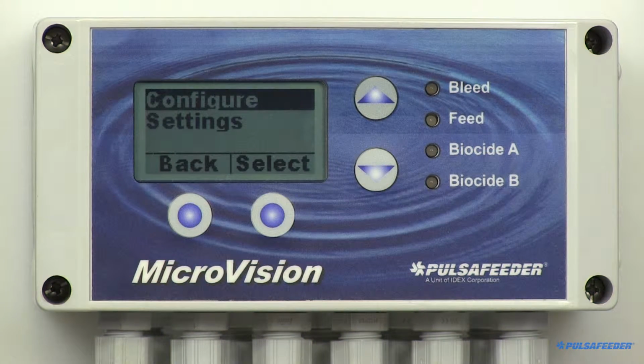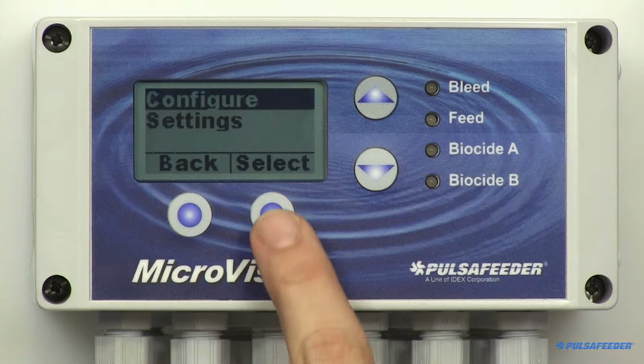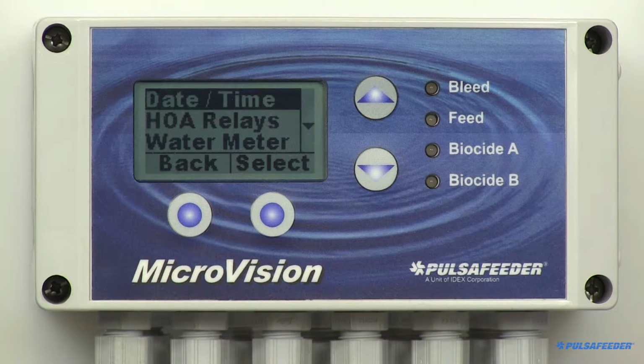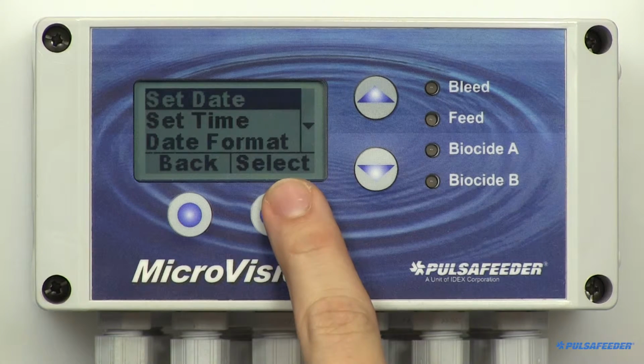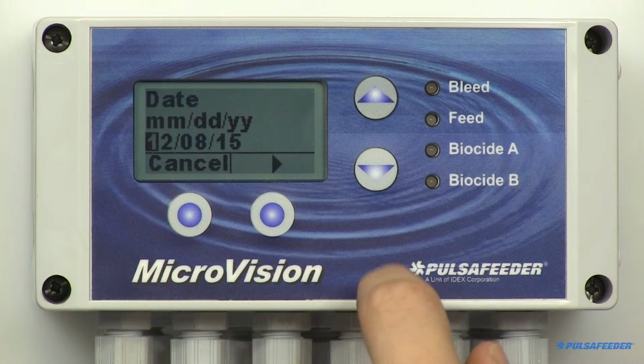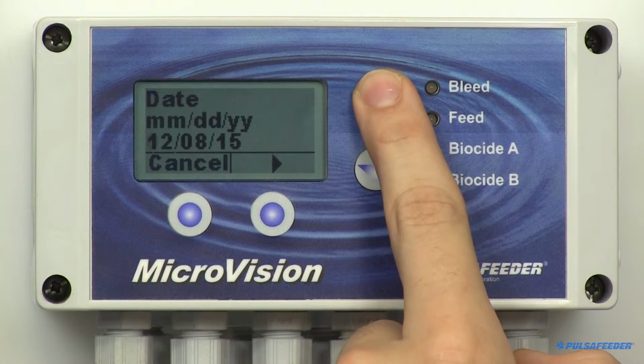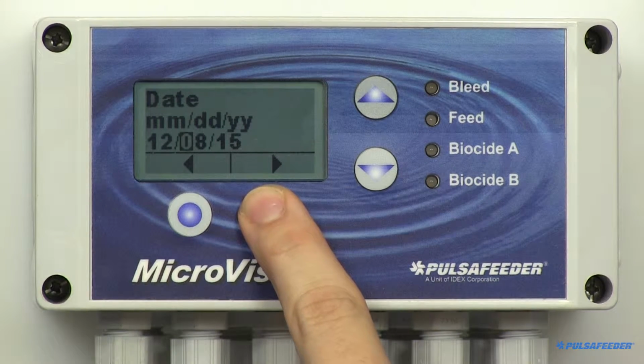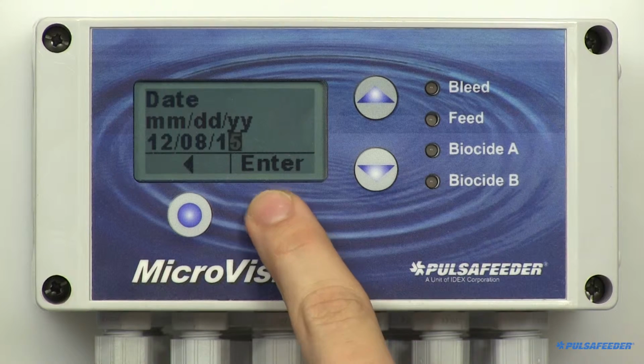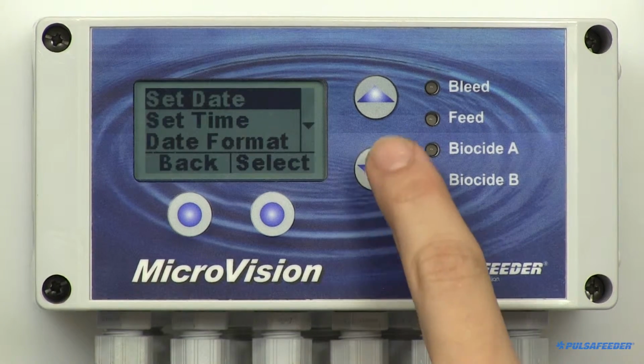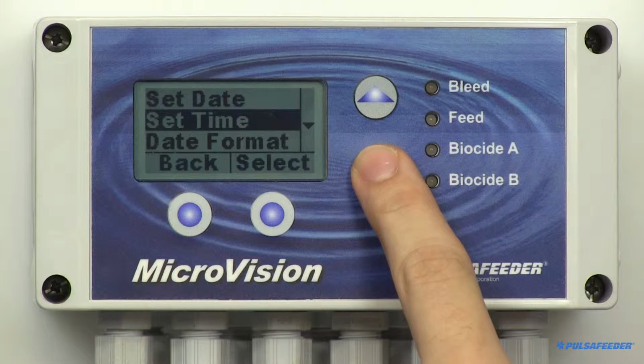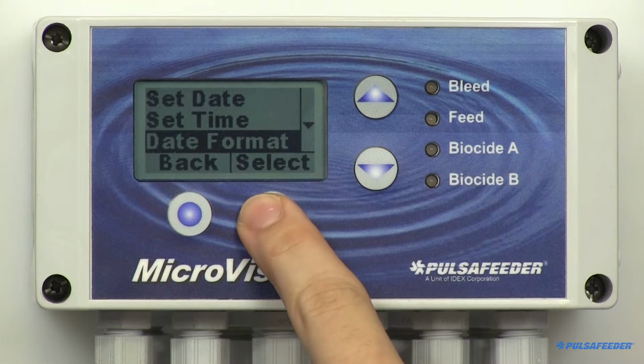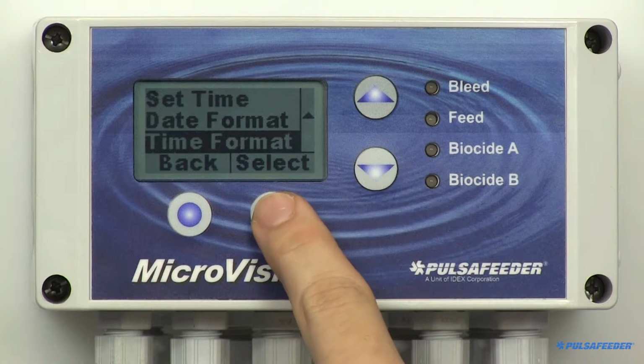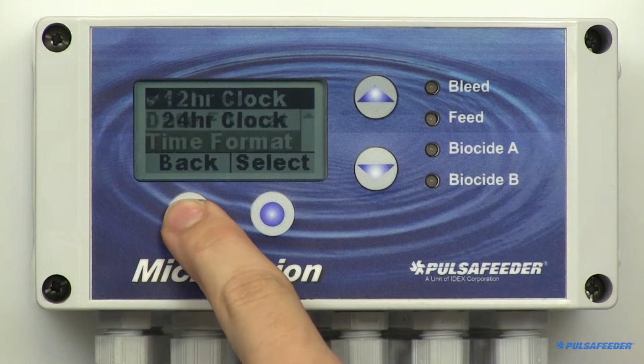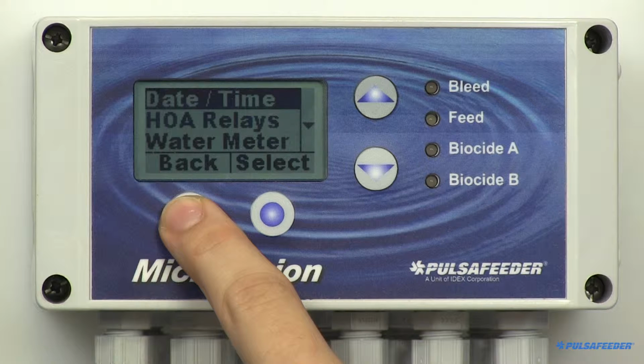Since Configure is highlighted, we can just press the Select button to enter this menu. Let's select Date Time, then set Date. To enter the date, use the up-down arrows and the right arrow soft button. Hit Enter, then OK, we're set. Arrow down to set the time. You can change the date format if you want. You can also change the clock format. Once these entries have been made, press the back button, HOA Relays.